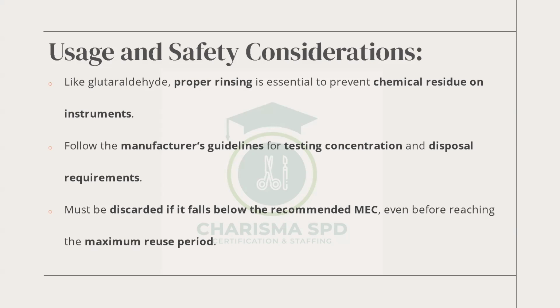You follow the manufacturer's guidelines on how to use the chemical by testing it to make sure that the concentration is there in the required amount to make sure that we are able to high level disinfect our instrument. Must be discarded if it fails. Now, if you are going to use it for 14 days, as I said already, it is not that the chemical should be there for 14 days and it was just changed yesterday. A new one was just put in yesterday. So today is fine. No, there is nothing like that. As I said, you don't know what happened. Maybe somebody is trying to sabotage you or sabotage the department by diluting it overnight or in the day, anyhow, sneak. So each time you want to use it, you must test it to make sure that it is working. It is good. Thank you.